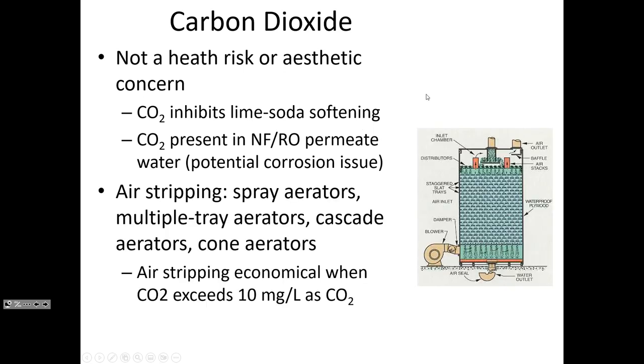There are ways to remove carbon dioxide through air stripping, which is economical. Installing a unit to blow air through the water is economical when the CO2 is more than 10 milligrams per liter. Otherwise, if you're doing lime soda softening, it would be cheaper to just add more lime to burn off the CO2. But when you've got more than 10 mg/L, you'd have to use so much more lime that it may be more economical to do aeration instead.